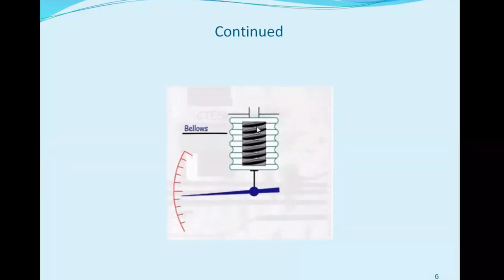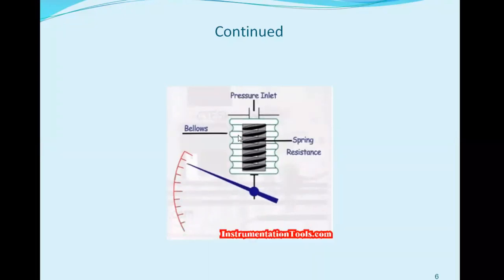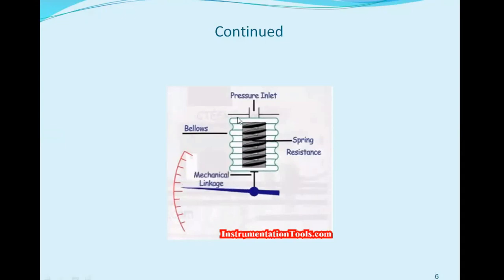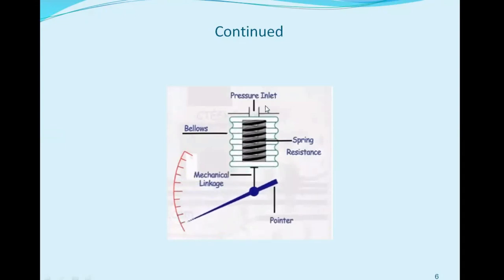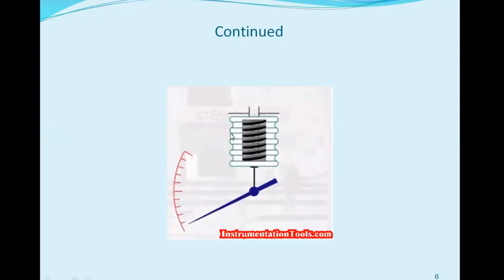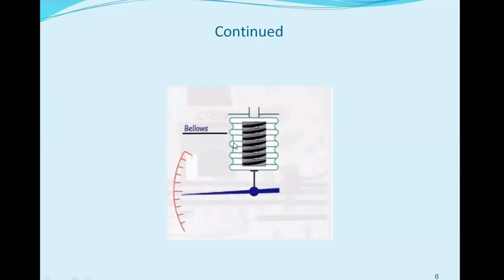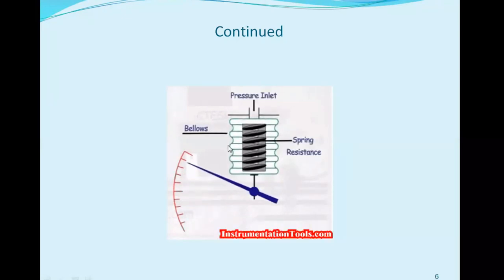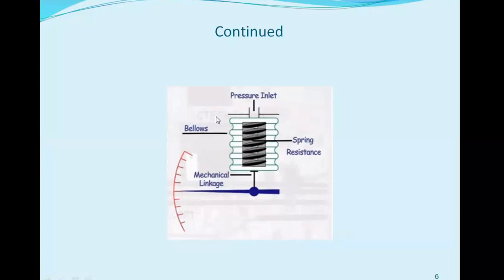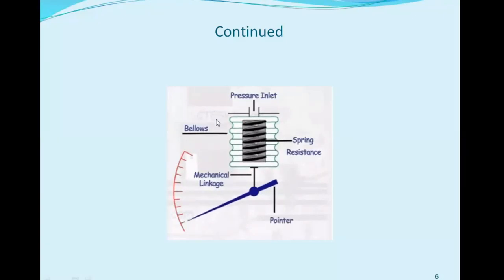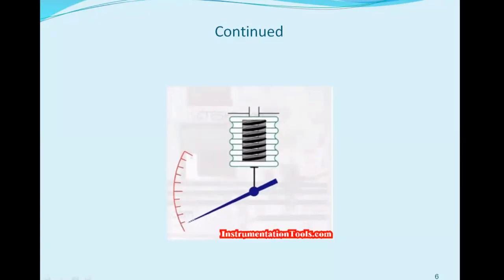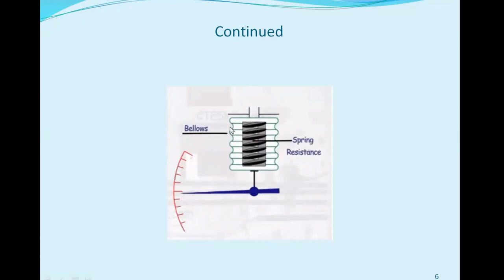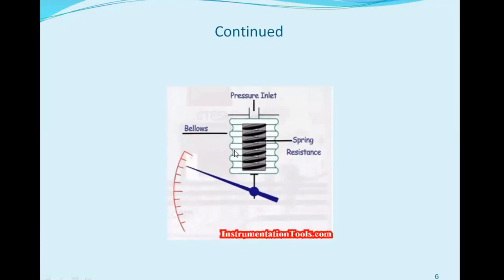So now this displacement, you can see in this video, the displacement is occurring now. The displacement depends on the number of convolutions, the number of folds. Okay, and in industry the number of folds may vary from 5 to 20. Suppose we are using 5 folds, 1 2 3 4 5.